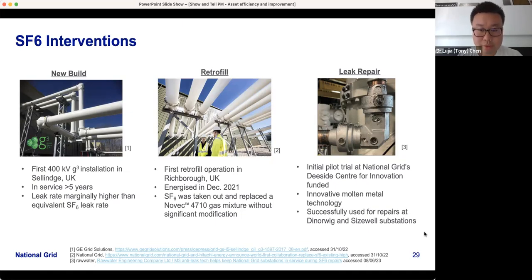So what National Grid has done in parallel is work with other partners to develop leak repair solutions. Initial pilot trials were already being done at the Deeside Centre for Innovation, using innovative molten metal manipulation technologies developed by Rawwater. You can see from the photo the ball valve - what you effectively see there is solder irons on top of the ball valve, which basically seals the majority of the gas leak from SF6. That has been successfully trialed at Dinorwig and Sizewell substations.